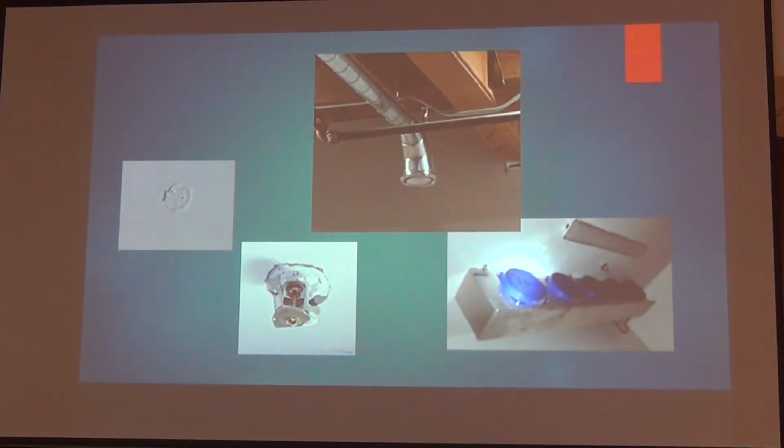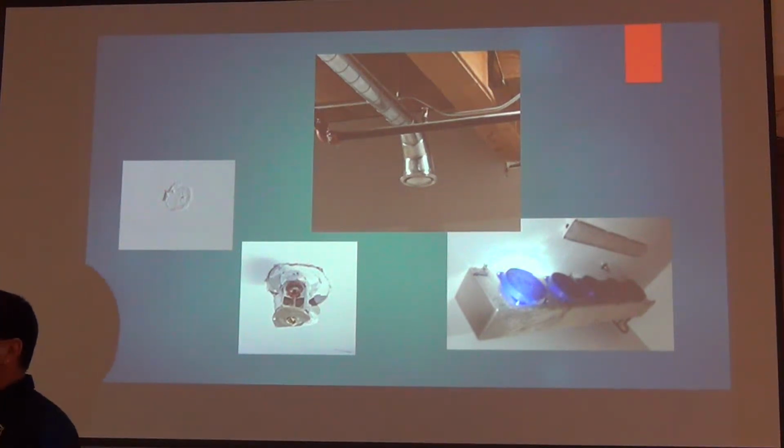There's your spiral. Whoever was asking me about a spiral pipe blocking it, that right there, if it was over another 2 inches, as per NFPA and the manufacturer, would work with it being in the middle of that 6-inch pipe. So what's the dimension from the pipe to the sprinkler head? What does it have to be? It would have to be 18 inches away from it. And it doesn't make any difference in diameter of that spiral? It does. This one's a 6-inch. This is where I say get with your manufacturer, because they do have what's called a wraparound effect of water.